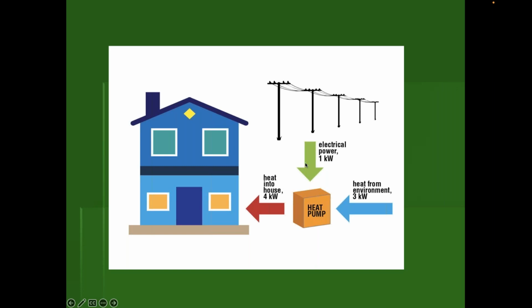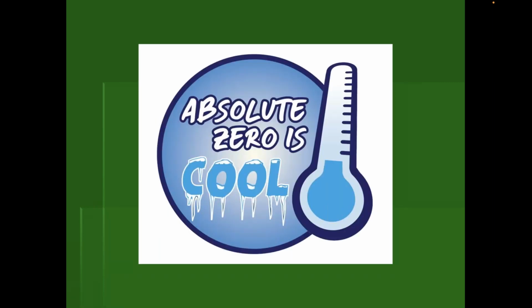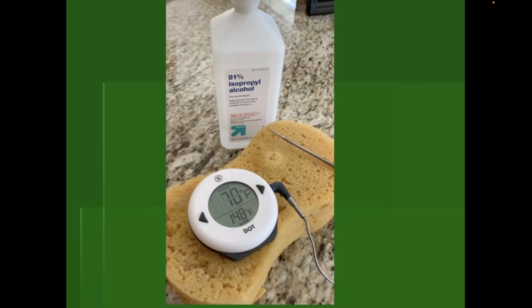And all we do is take our heat pump, which basically takes 1 unit of electrical power from the grid, and then uses that through the refrigeration cycle to extract that heat out of the environment. So we get 3 kilowatts of energy from the heat that's already in the air, and then we get 1 kilowatt from the grid, and that produces, for example, 4 kilowatts of heat going into our homes. And if we had no heat in the air, absolute zero would be like 459 degrees below zero. So there is quite a bit of heat in the air, as I said, and all a heat pump does is use the magic of refrigeration to extract that heat out of the air. So let me show you an example of this, and then I'll ask for some questions.